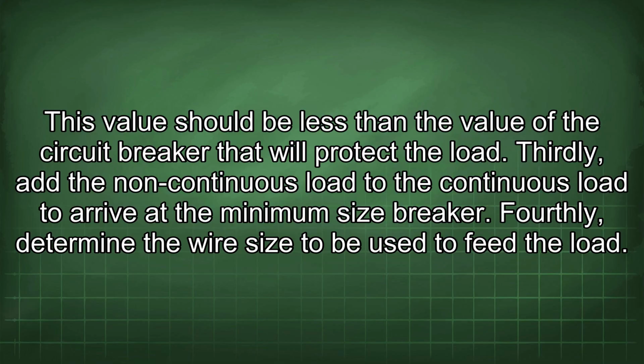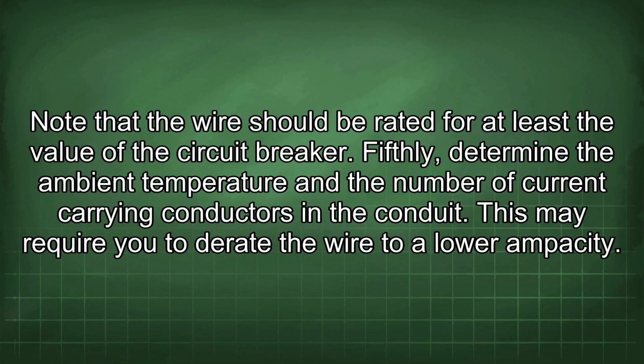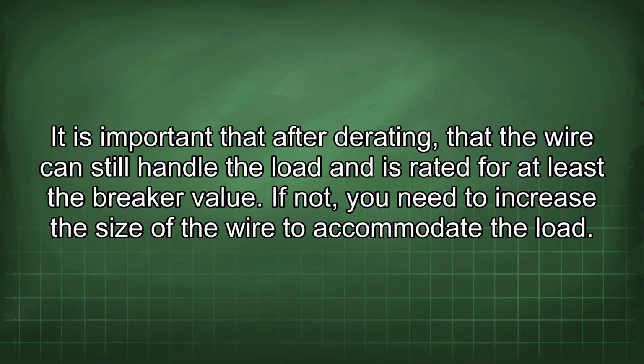Fourthly, determine the wire size to be used to feed the load. Note that the wire should be rated for at least the value of the circuit breaker. Fifthly, determine the ambient temperature and the number of current carrying conductors in the conduit. This may require you to derate the wire to a lower ampacity. It is important that after derating, the wire can still handle the load and is rated for at least the breaker value. If not, you need to increase the size of the wire to accommodate the load.